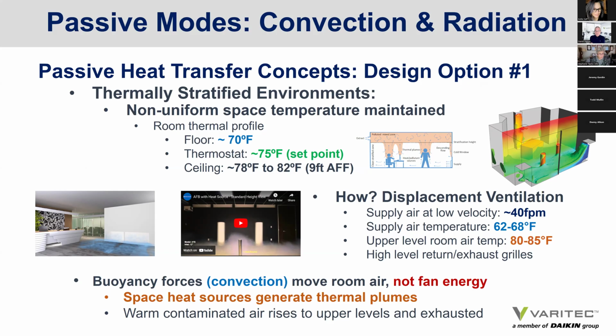The temperature at the floor will probably be at about 70 degrees, with a thermostat set point of 75 degrees. And then we want a warmer air region in the upper levels of the space at between 78 to 82 degrees. It can be more depending on how tall the ceiling is. What is the space sensible load? There are a lot of different factors depending on the application. So how do you create a thermally stratified environment?